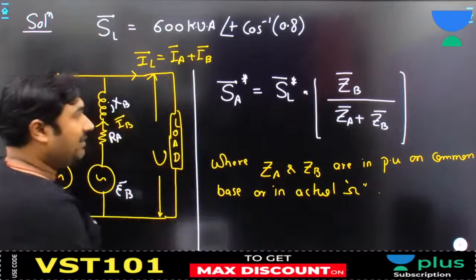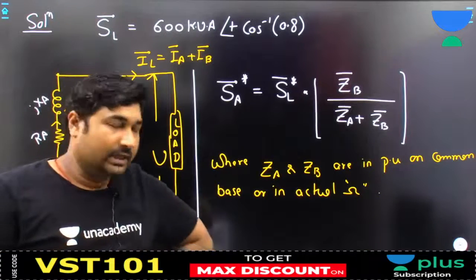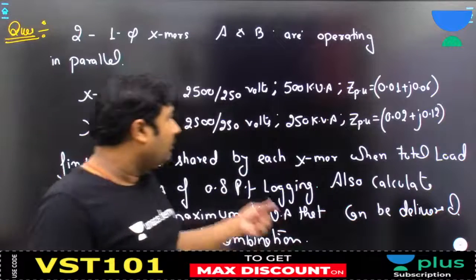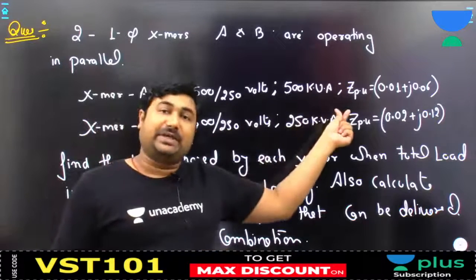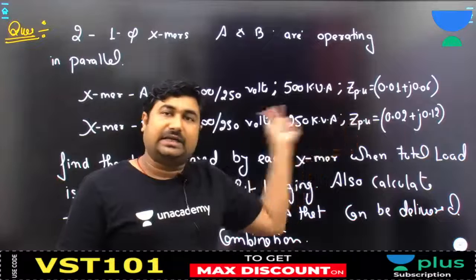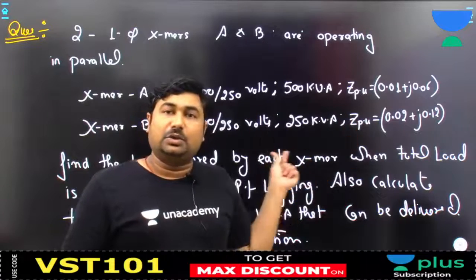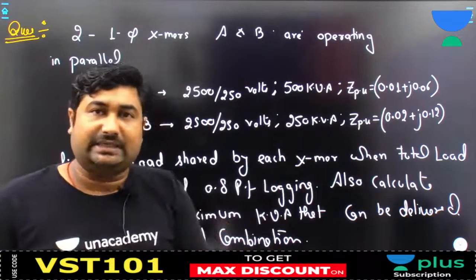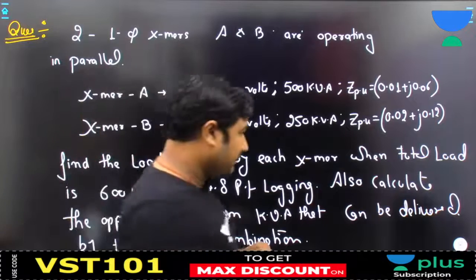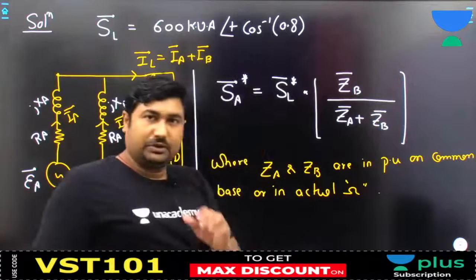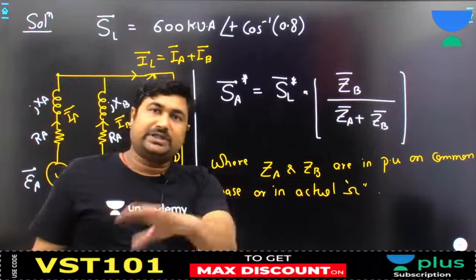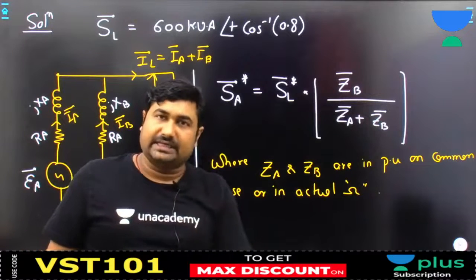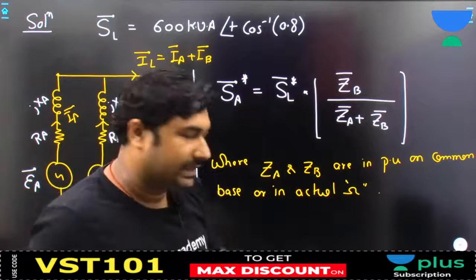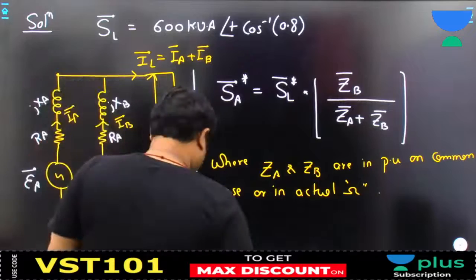So first of all, we have to select a common base. It is best to take the rating of one transformer as the base value. It is in your hand. You can select any one of the two transformer ratings as the base rating. So you can just suggest to me which transformer rating we have to take as the base. Whatever you want, you can take that one. I am taking 500 kVA as the base.